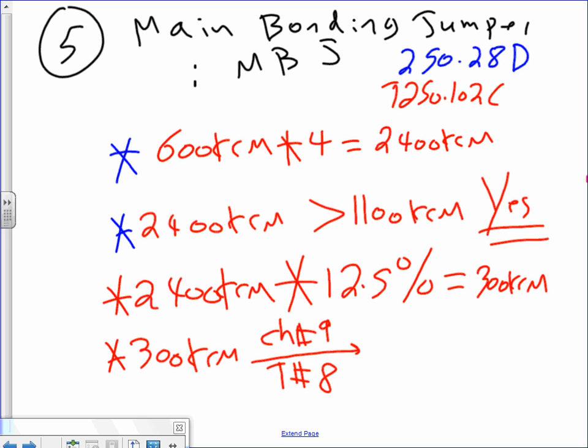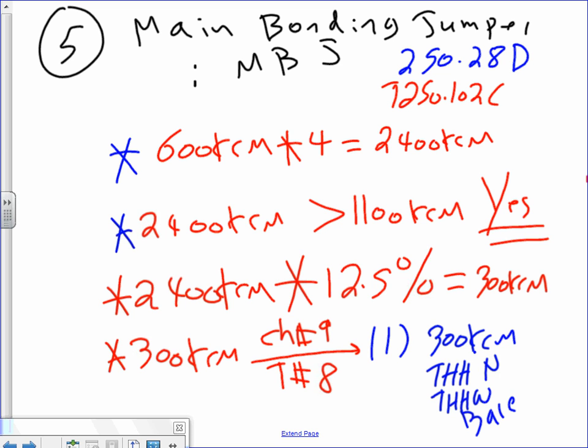So what size, gentlemen, then? We verified, what did we do? We verified that this one is one conductor, 300 kcm. What insulation? THHN. Now, since it's inside the switch gear, and it's bonding, you can use THHN or THHW, or how about bare? Do they spell bare right? B-A-R-E. Yep. As in naked, bare, or bare conductor.